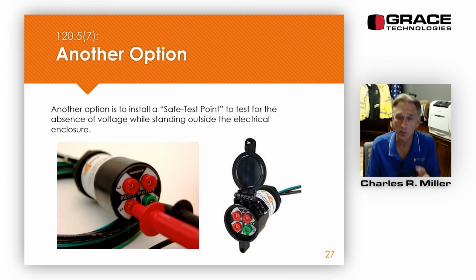All right, this is another option. I like this option. This is really a remote test point. It can be installed on the door. It can be installed on a fixed panel that is not opened and closed all the time. It can be installed in a junction box right beside the equipment. Grace calls it a safe test point. We can use this to test for the absence of voltage outside of the cabinet before ever opening the cabinet up. And in this, you are doing the testing yourself, meaning you're using your own meter.